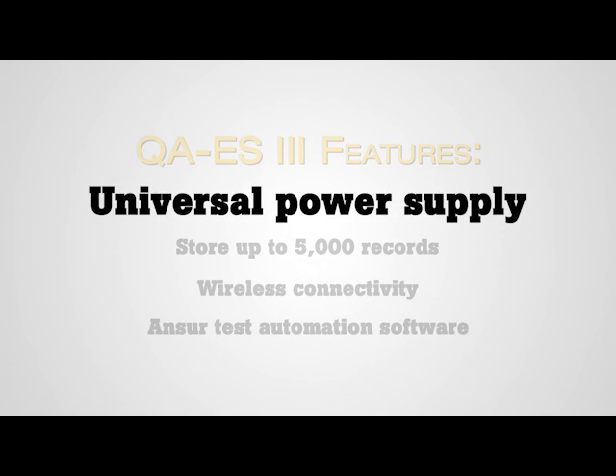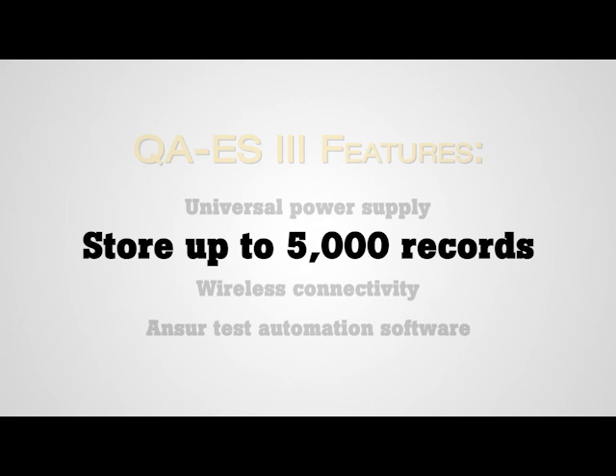Featuring a universal power supply and in compliance with global standards for testing electrosurgical devices, including IEC and ANSI-AAMI, the QAES-3 can be used worldwide. It can store up to 5,000 records, making it convenient to store results and retrieve later.